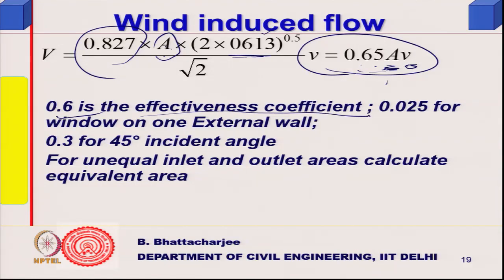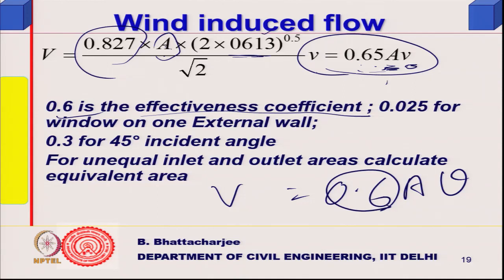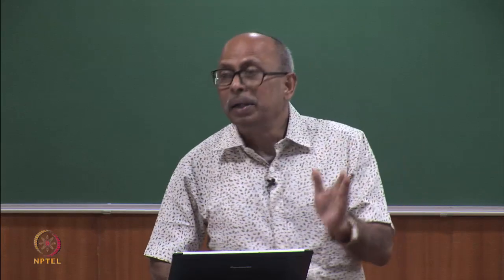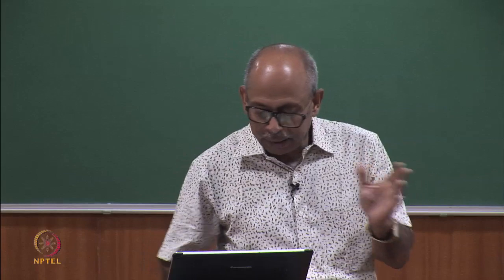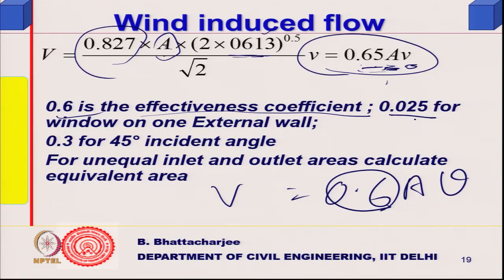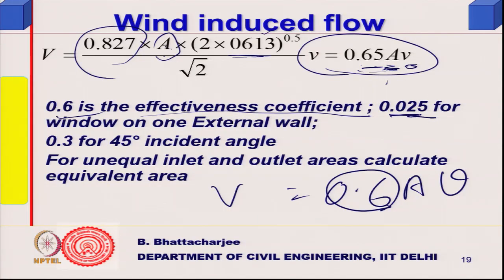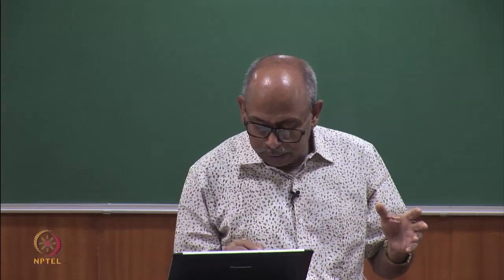This constant 0.6 is called the coefficient of effectiveness. So flow in m³/s equals 0.6 times A times outside velocity — for cross ventilation with windows on both windward and leeward sides. For a window on only one side (no cross ventilation), the value is 0.025. For a 45-degree angle of incidence, it is 0.3.